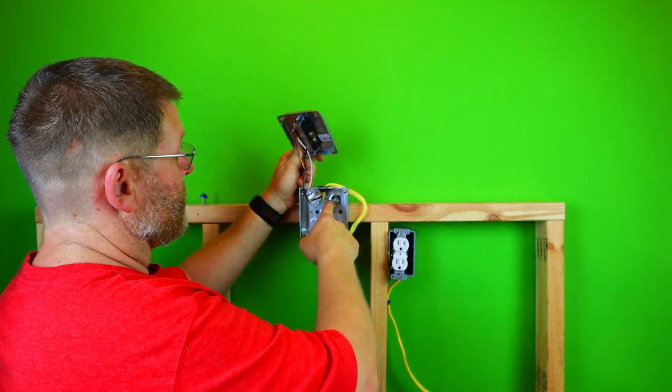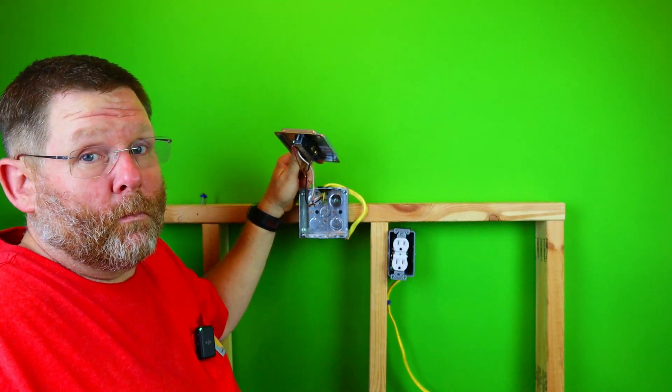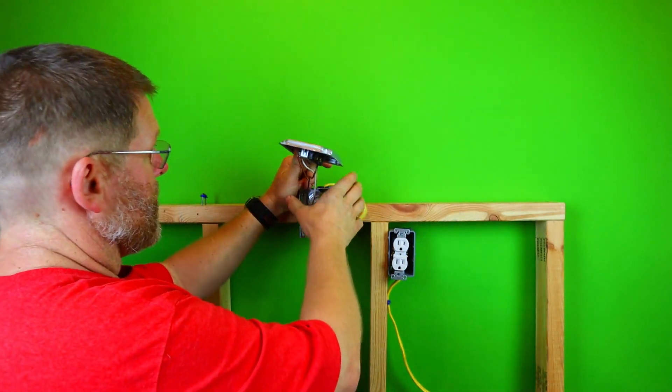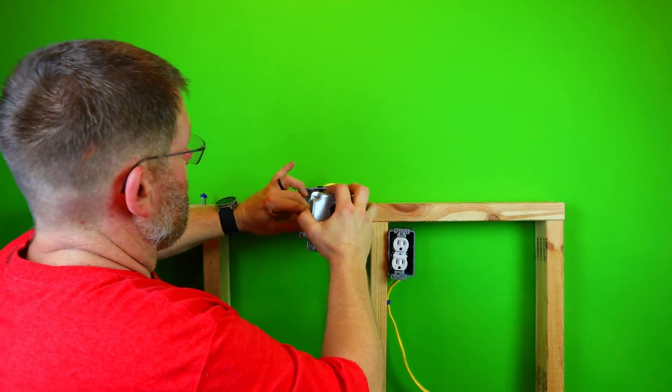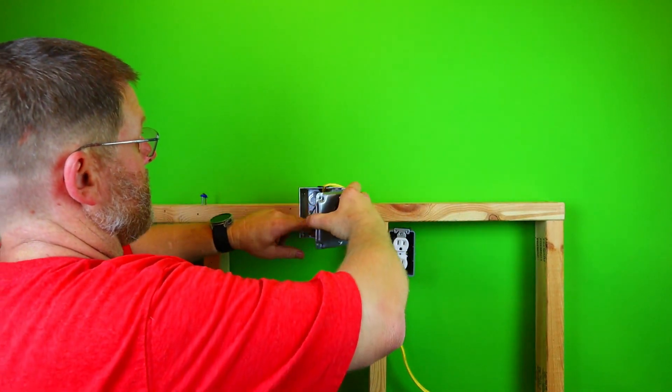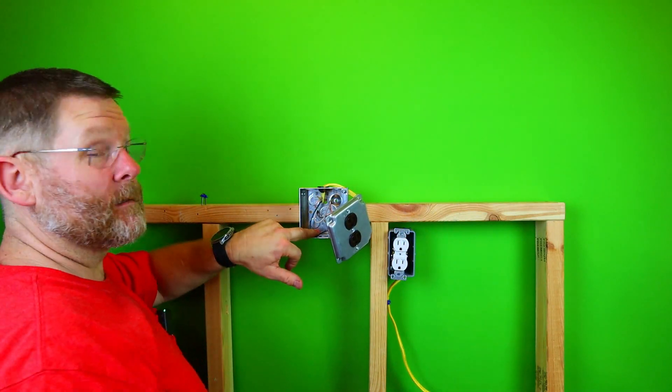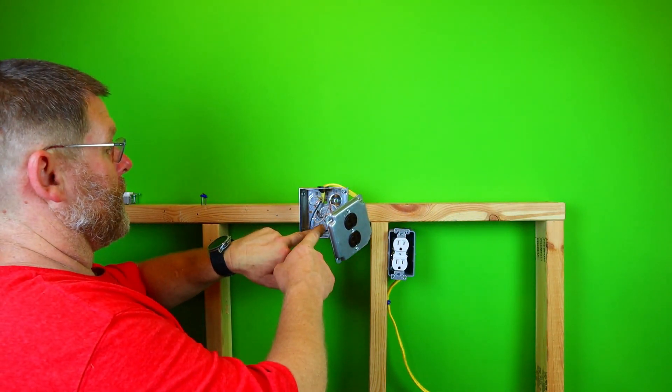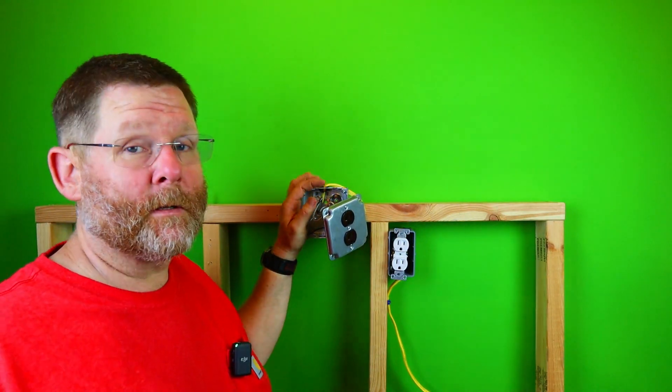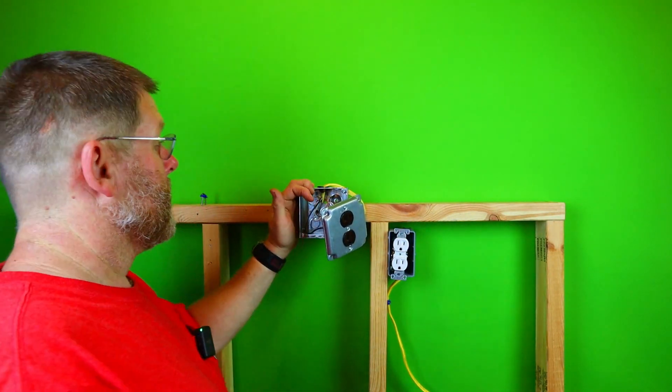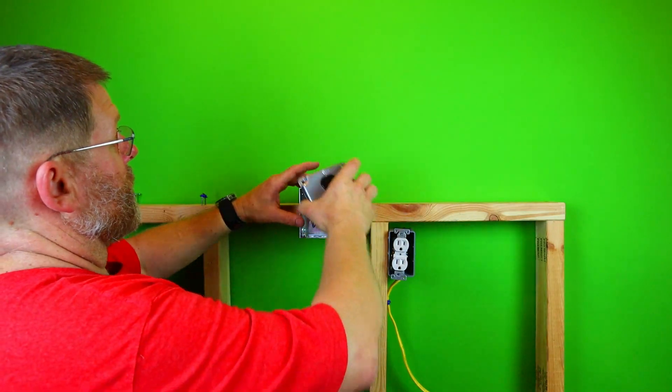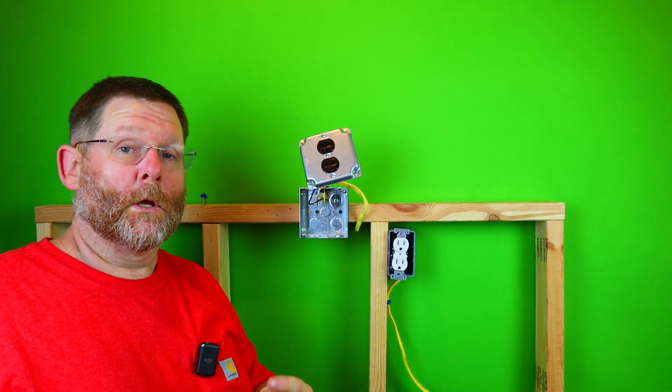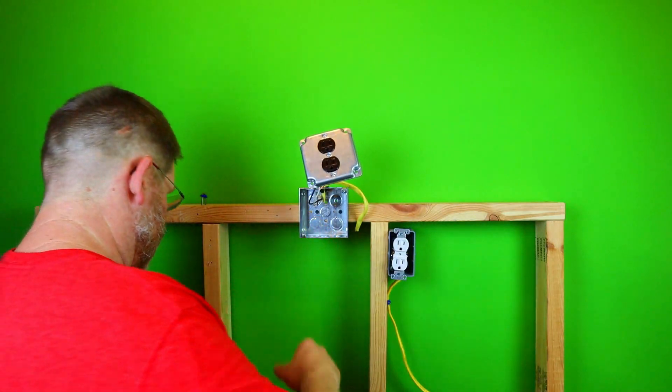So my opinion on grounding is this: I agree code says you don't have to put a ground screw in there. However, if you do not and you pull this out, let's say you pull it out and the ground is fine but you've got a hot wire sitting like this, well, if you go to touch this box and you're grounded, you're going to get shocked, plain and simple.